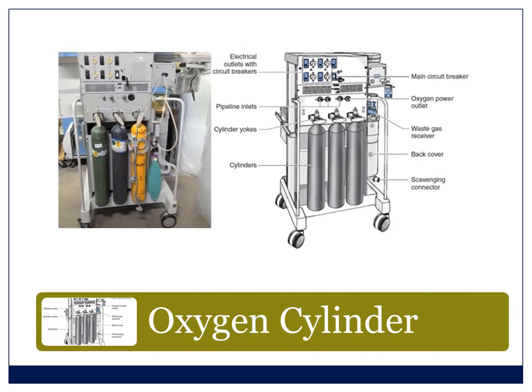Check this every time. Check the oxygen cylinder at the back of the machine. These things are usually turned off because otherwise they slowly leak and empty. So you have to go around the back of the machine. You have to open the cylinder, the oxygen cylinder. Then you come around the front of the machine and look for the pipe, the pressure in the cylinder, which will read on the screen somewhere on the anesthetic machine. A full one is about 137, but it must be at least 50. And once you've checked that, then you go around the back again and you close it so that it doesn't leak out. And I generally just do that at the beginning of the day.